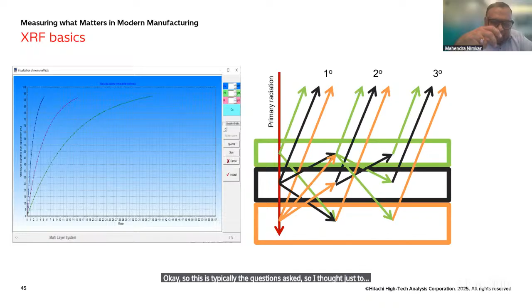For example, if people ask me, can we do 50 micron, can we do 100 micron? It depends on the element or the coating. If you see these curves, they increase and then become a plateau. What I want to convey is that for every element, based on its coefficient of absorption, how much X-ray is absorbed and how much is transmitted or reflected back decides the maximum thickness I can measure. In some cases, you can measure, let's say, 30 micron. In some cases, you may not even measure 2 micron. This is typically the question asked, and I hope what I'm saying makes sense. Something similar is happening, I'm just explaining with the pointer.